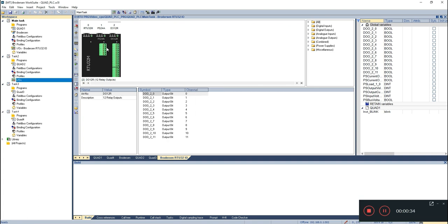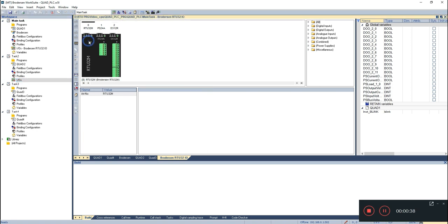As it is here, you can see the whole thing happens in the CPU. That means you only have one CPU, but that CPU can run 4 different PLC programs. But you still have one piece of hardware. Remember that. So don't try to distribute your IOs across, because it's still the same CPU. If you want to do that, buy more CPUs. Okay, that's the first step, and the most important step.